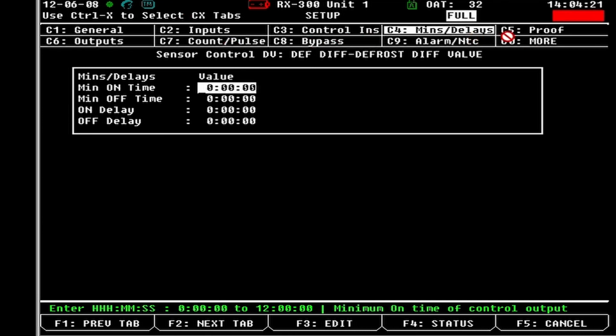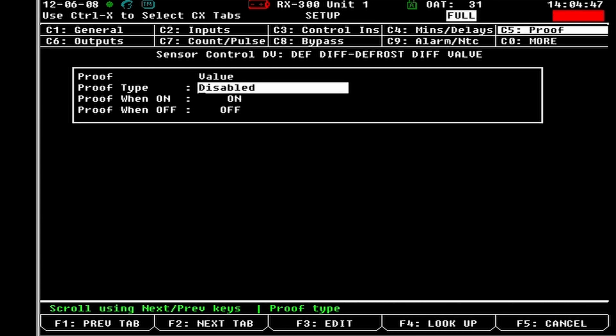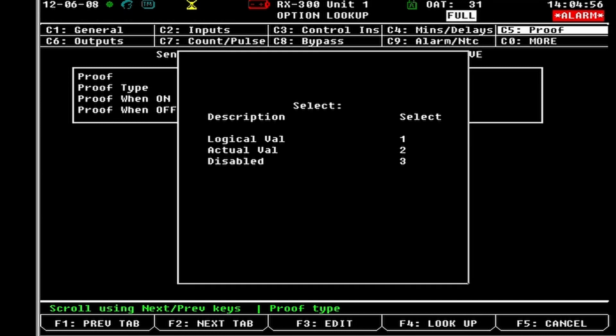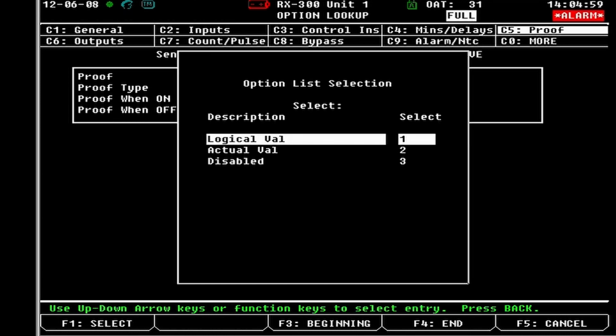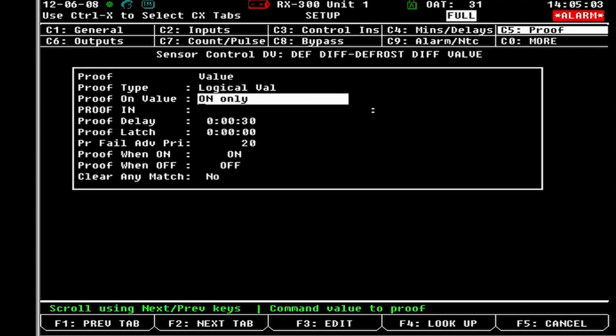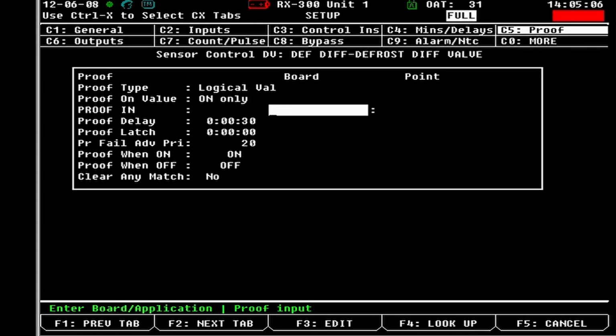So you have your minute delays. So you have minimum on time, minimum off time, and then your on delay and off delay. So I mean, you could use this for a compressor, an unloader, a single system if you're doing some fans, if you're doing some defrost termination. So anything that is a digital sensor. So if we go to the next tab, we got our proof. So you could have a proof tied into this. So you could have a proof type and a proof input. So if you hit look up under here and you hit logical value, so you have a proof input. So you could have a separate, it tagged another input in here.